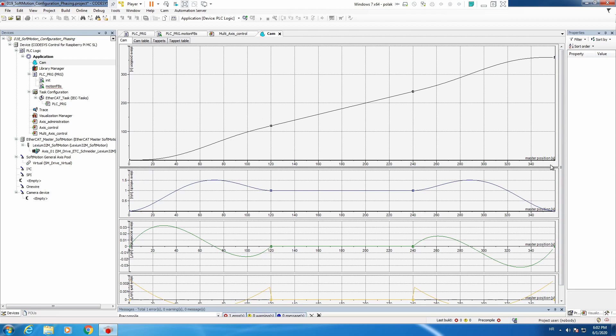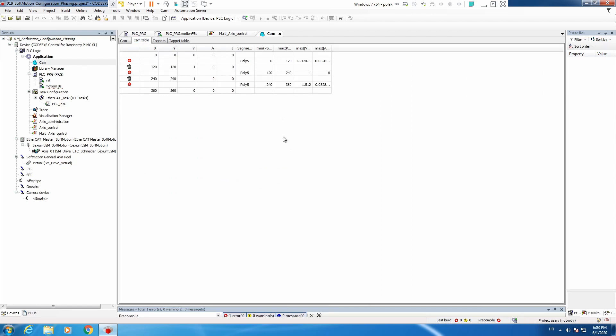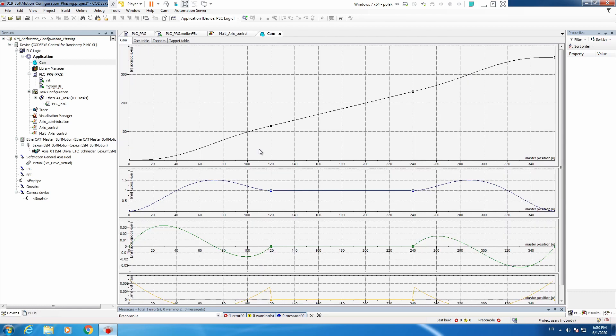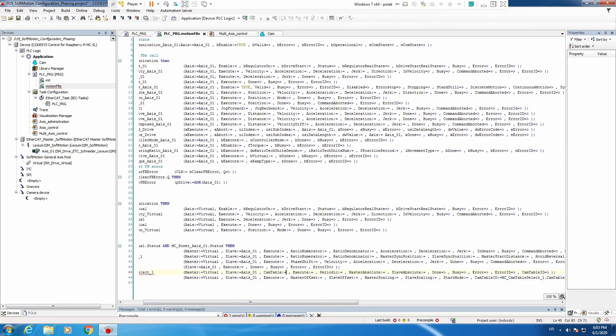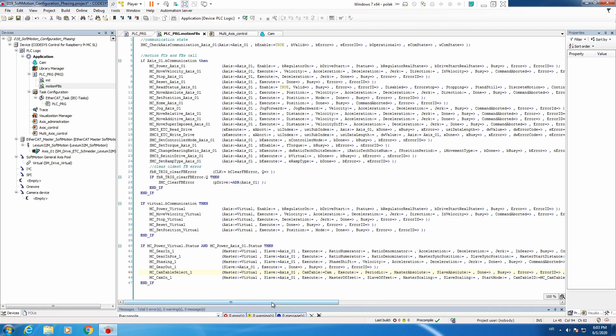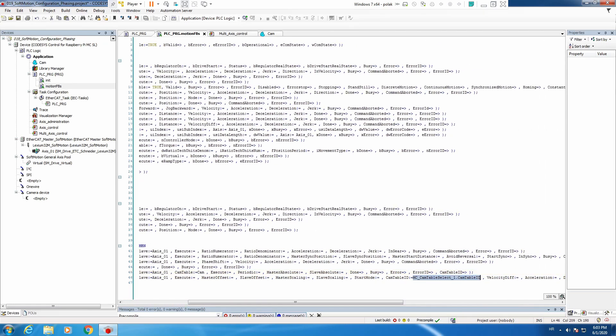The lower part is the master axis and vertically you have your slave position. If you click on the cam table, you will see that this matches to our points on our graph. We can run exactly this cam table and will not change anything. When you create your cam table, go to your function blocks and on MC Cam Table Select, you just need to say what your cam table is — this is the name. So you just put 'cam'. You need to select on MC Cam In the cam table ID from your MC Cam Table Select.